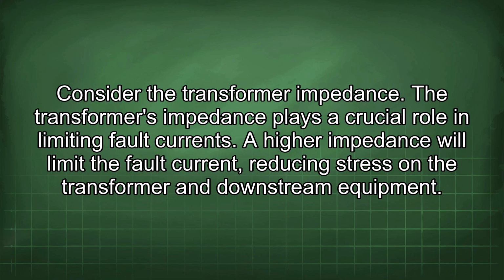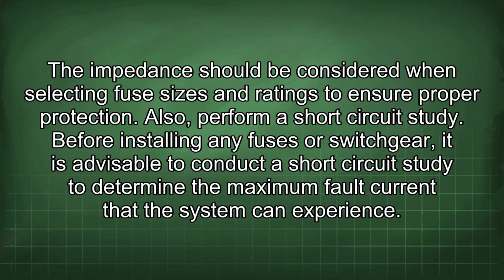The transformer's impedance plays a crucial role in limiting fault current. A higher impedance will limit the fault current, reducing stress on the transformer and downstream equipment. The impedance should be considered when selecting fuse sizes and ratings to ensure proper protection. Also, perform a short circuit study.